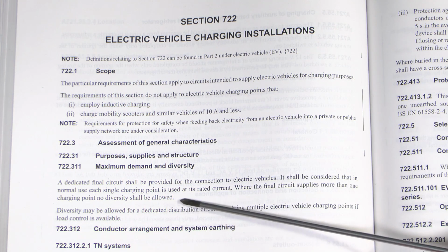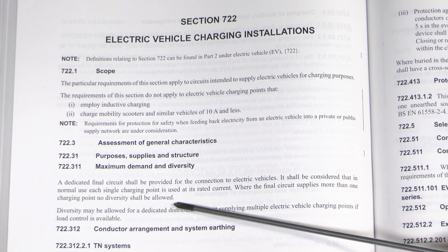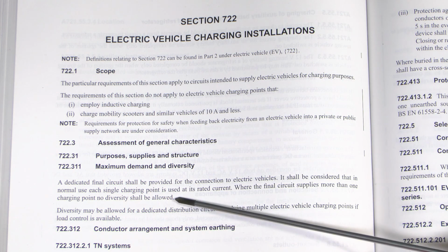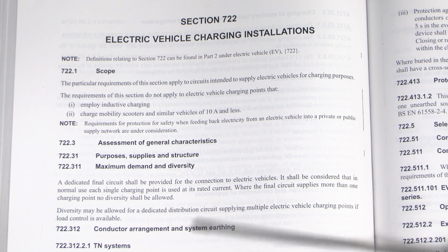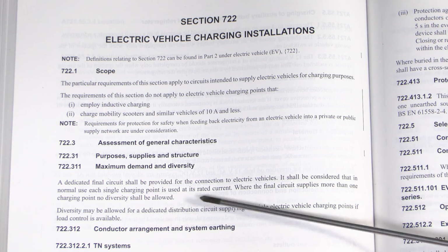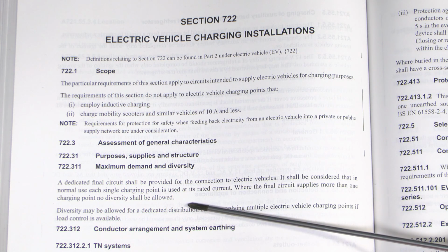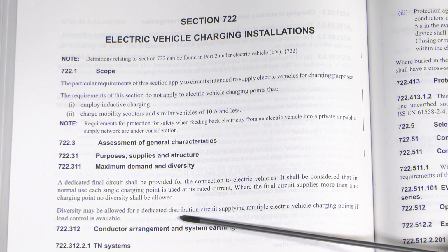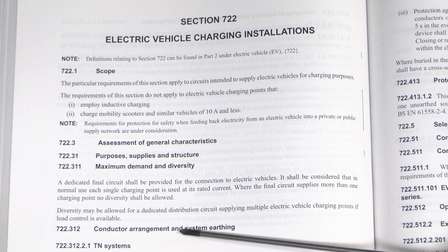Now diversity in terms of a domestic installation isn't particularly going to be relevant because most people are going to have one electric charging point, but certainly in places like, say, a car park or something where you may have a whole row of the things, important to realise that if it's 32 amps per point and you've got 10 of them, then that's going to be 320 amps of possible demand there, and of course the circuits and equipment needs to be designed to deal with that.